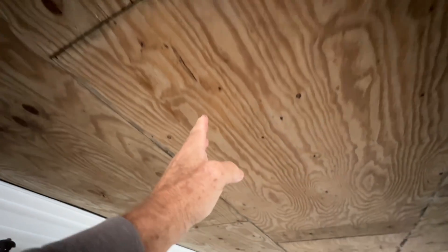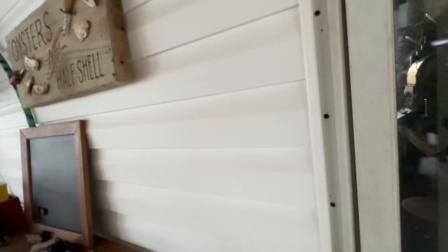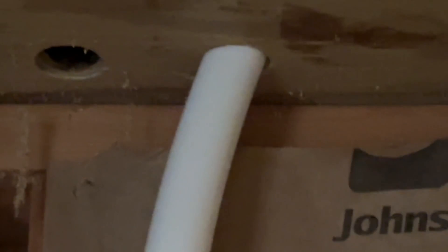The water goes up into the crawl space, so I was able to hit the main line right there and go overhead, dropping it down into this mechanical room. There's one-inch line going up and tapping in, and another one-inch line going back out. That's the supply side and that's the outlet side going back to the water heater. I basically cut a three-foot section out, put an elbow, routed it into the mechanical room, and then back out to the water heater.